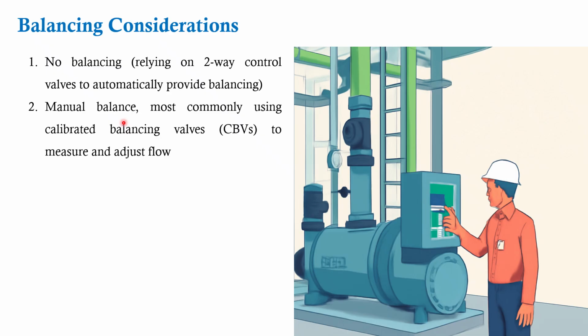The manual balancing valve in the headers, risers, or the AHUs, and if a manual balancing valve is there, how it is being calibrated and balanced. It also needs to be ensured that it has been calibrated for the given flow, even if it is installed at the AHU level or the riser level. If there are three blocks, three buildings, it has been installed at the three levels. If my AHU is already integrated with the pressure independent balancing control valve, in that particular case, putting a manual balancing valve in the riser is not going to be required, which people put. I will make a separate video on that particular dimension for the benefit of you all.